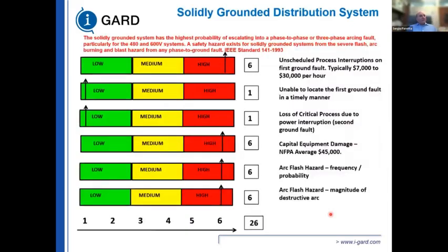So we applied the safety meter to this. Unscheduled process interruptions: you don't know when you're going to have a ground fault, and when you do have a ground fault, you're going to trip. So that's very high. You are able to isolate the first fault because you have ground fault protection. Now it just matters how much of your system you are going to lose. If you put ground fault protection on each one of your feeders, you're going to lose a small part of your feeder. However, if you just put ground fault protection on the main breaker, you're going to lose the entire system. Loss of critical process due to power interruptions is low.